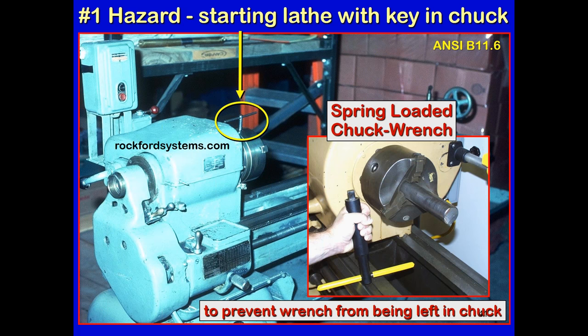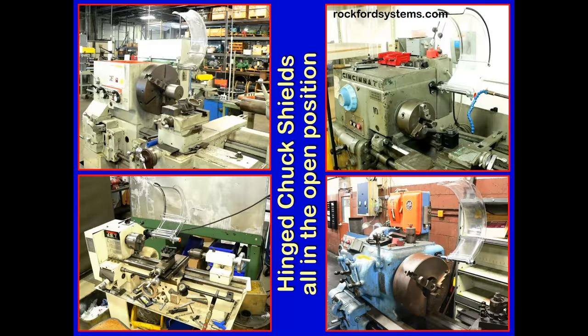One more thing. The top left corner of this lathe is a manual motor starter with stiff mechanical clicks to turn the machine on and off. Problem with a manual motor starter is it doesn't give you dropout protection. In other words, if the machine is running and you suddenly lose power to it, power's off for 15 minutes, power comes back on, yes, with this machine, it'll restart unexpectedly if the start button is engaged. With a magnetic motor starter, no, you'll have to come back to the motor start button. So I'll show you some magnetic motor starters later, but this one is mechanical and should be replaced.